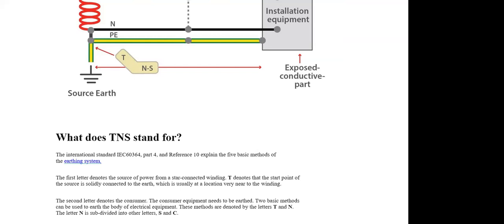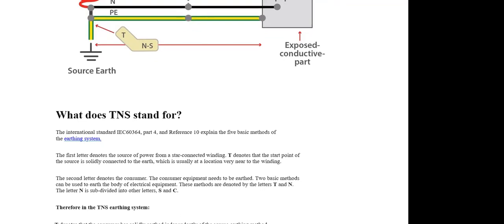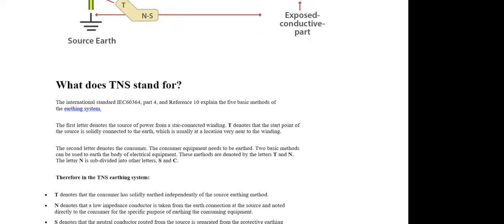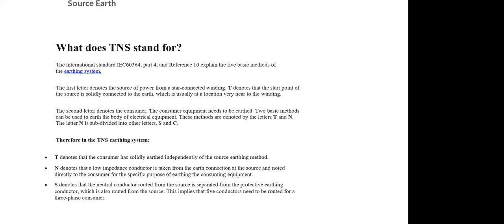The second letter denotes the consumer. The consumer equipment needs to be earthed. Two basic methods can be used to identify that. These methods are denoted by the letters T and N. The letter N is subdivided into other letters, S and C. So T denotes that the consumer is solidly earthed independently of the source earthing method. This is mostly connected to the distribution system, but generally in infrastructure, this TNS system is followed.